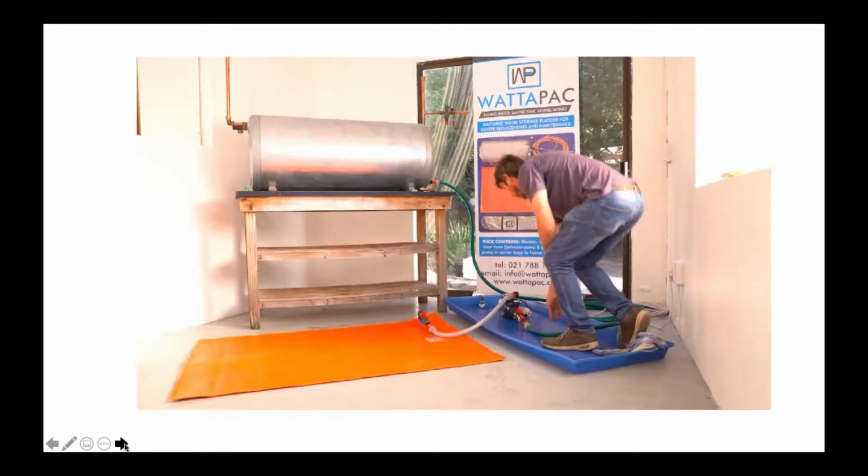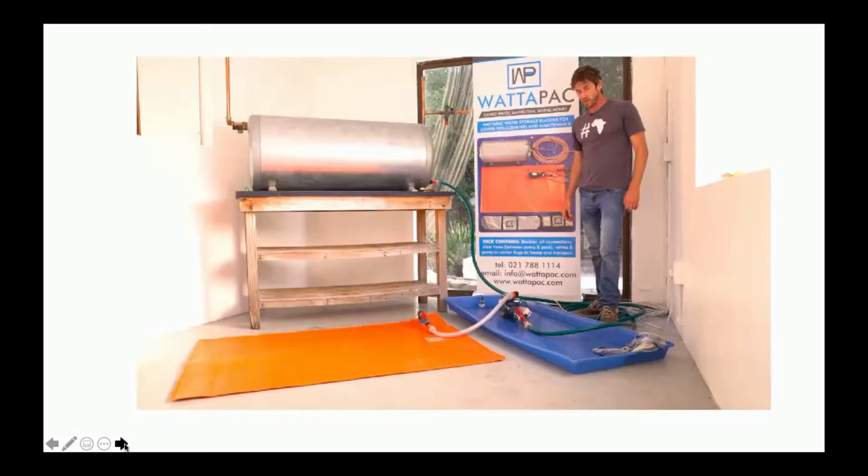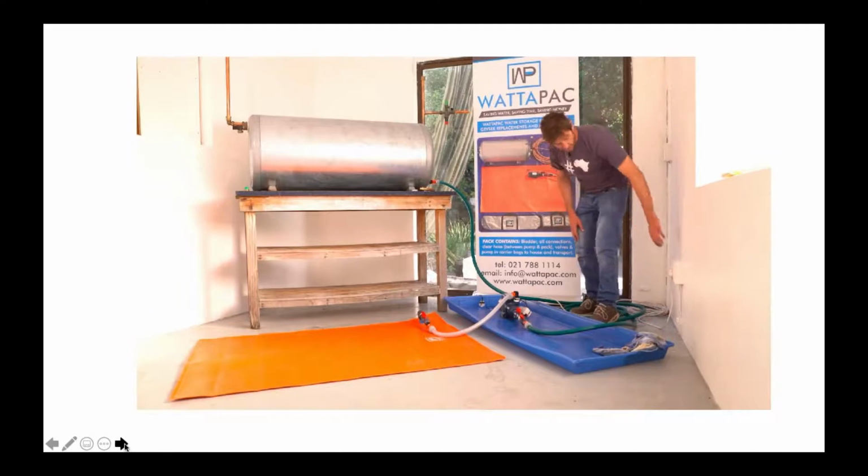Here we've got the water coming through the clear hose, which is a protective measure so that we don't put dirt in the bladder. Or if you're doing an element change, once you see the brown water coming, you simply stop the process and you can discard the brown water. If you're doing a geyser change, the minute you see the hot water, the dirty water, you simply stop the process and discard the dirty water. Then you turn it on, and this process should take 7 minutes.